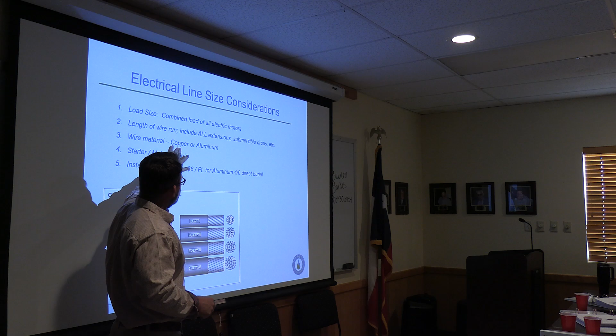So you would want to take all of your load sizes combined. You need to calculate for your length of wire run, including all extensions and all the drops to each of the motors. You need to decide whether you want aluminum or copper. In every case, copper is a better conductor, and in every case, aluminum is substantially cheaper. And so you're going to weigh that. Also, I don't know of scrappers who are really hauling much aluminum off on purpose, so you might be strategic on where you place the aluminum and copper.